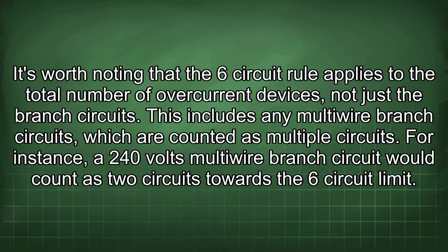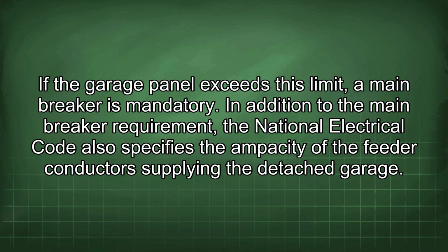It's worth noting that the 6-circuit rule applies to the total number of overcurrent devices, not just the branch circuits. This includes any multi-wire branch circuits, which are counted as multiple circuits. For instance, a 240 volts multi-wire branch circuit would count as 2 circuits towards the 6-circuit limit. If the garage panel exceeds this limit, a main breaker is mandatory.